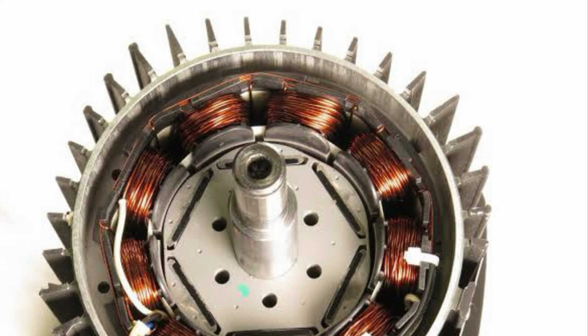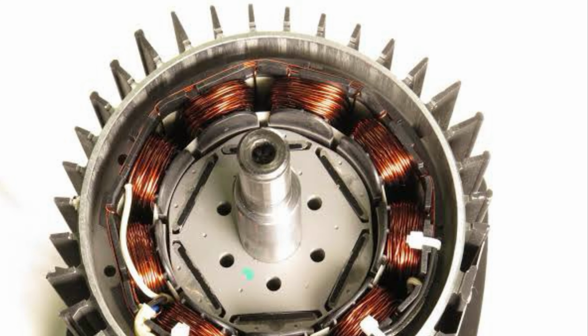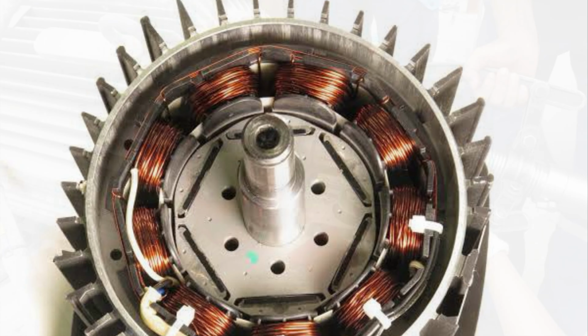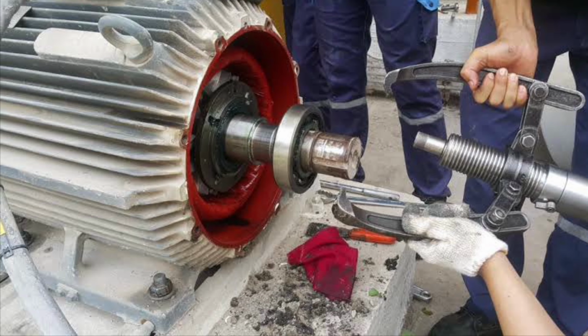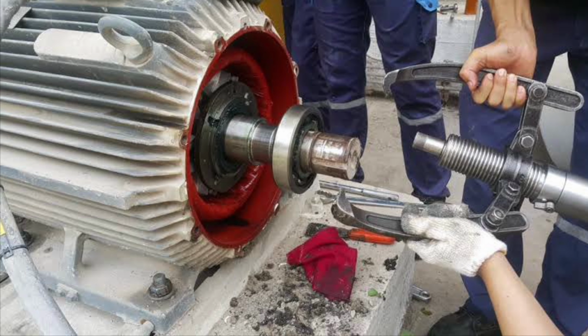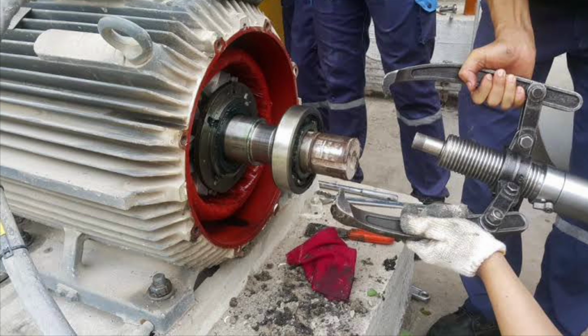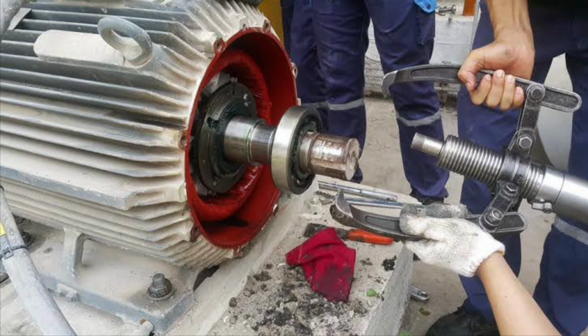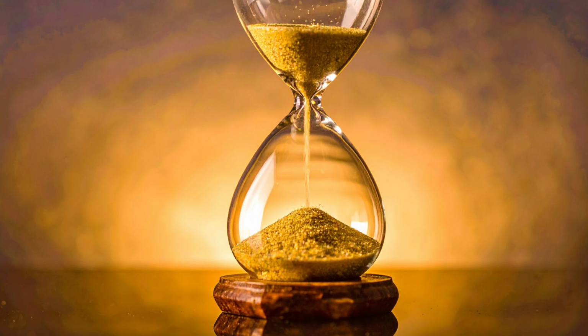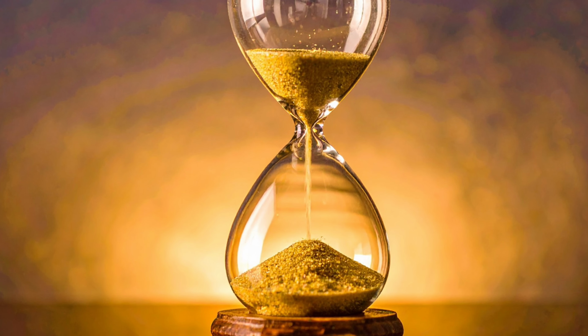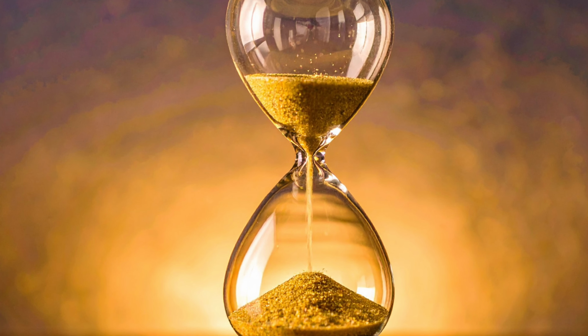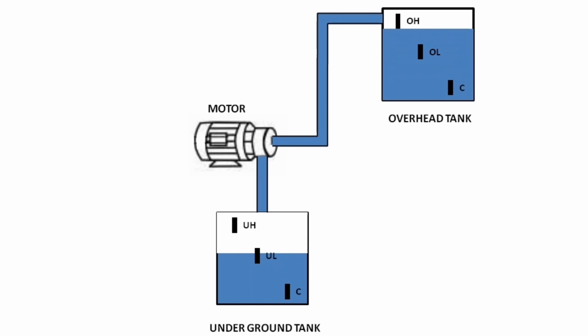This device has a current based dry run protection. If the motor runs without water, then it takes a lower ampere than its load ampere. This device stops the motor in dry run condition and protects it from burning. This device also has an on delay timer, off delay timer and cyclic timer. This model comes with 6 sensors.